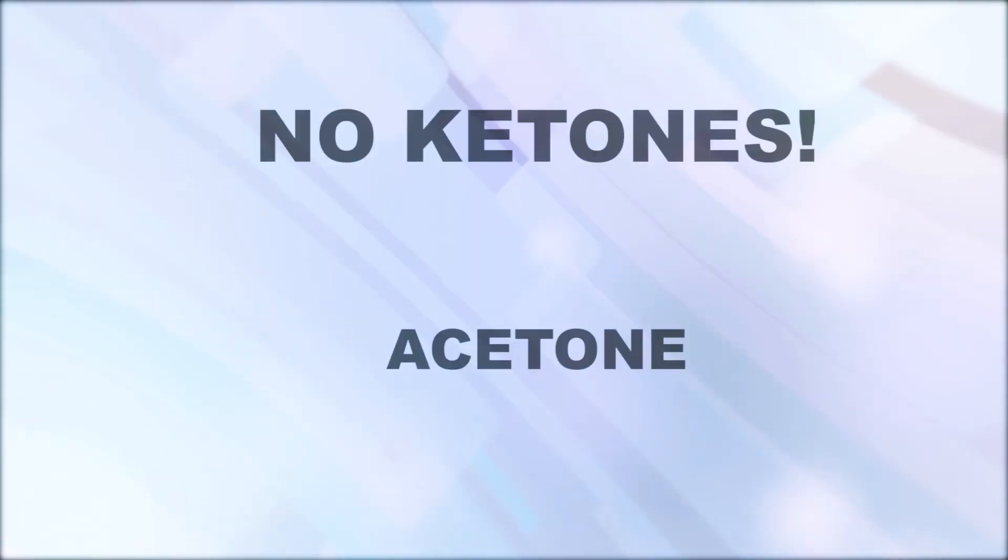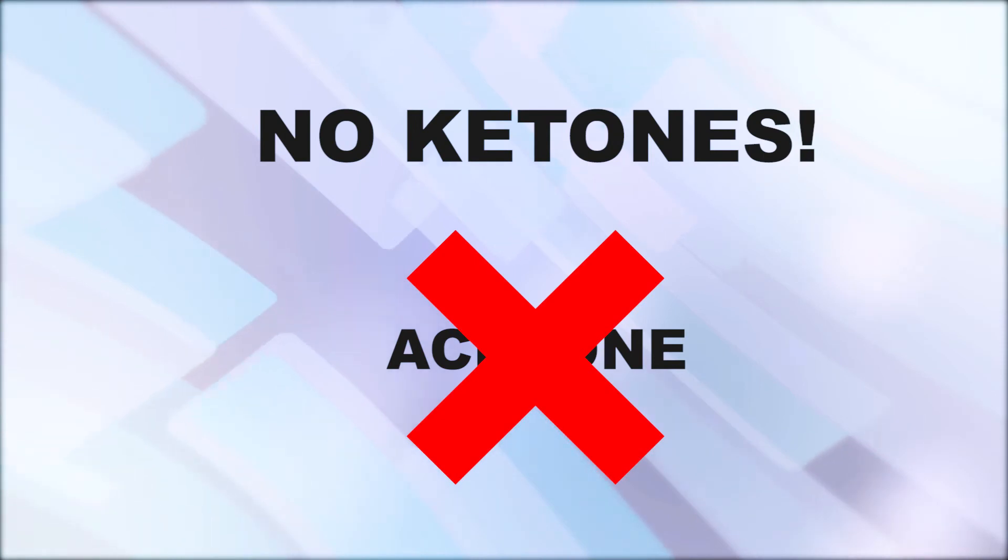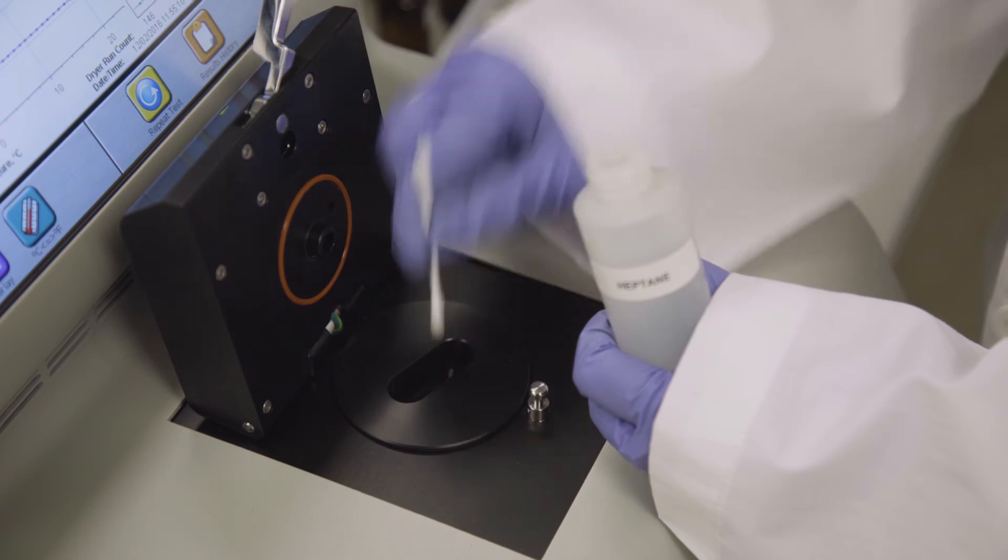Never use ketones such as acetone. These solvents can damage the analyzer. The cup may have to be cleaned with solvent a few times.